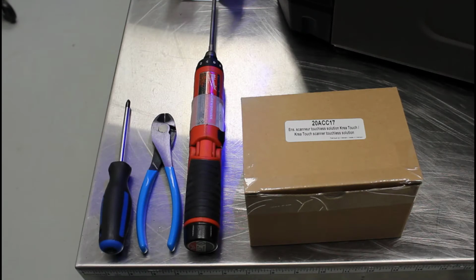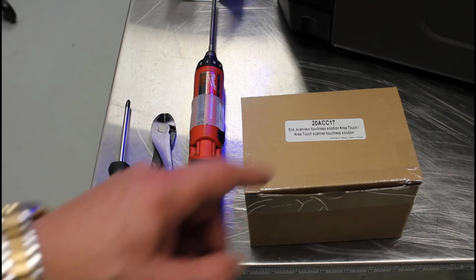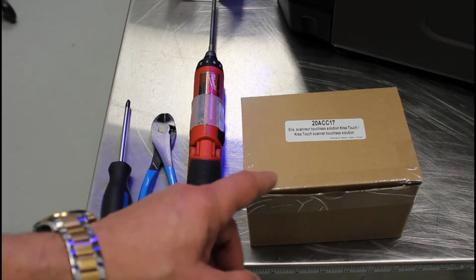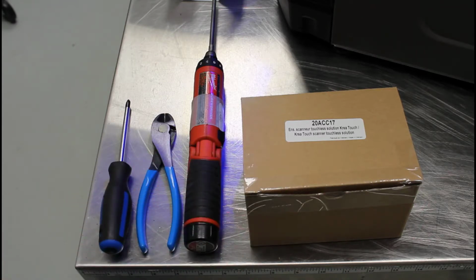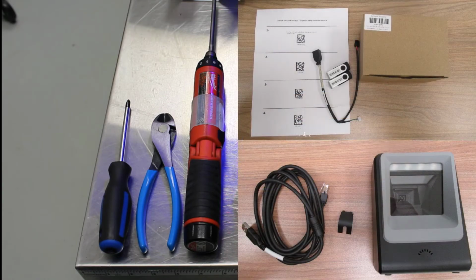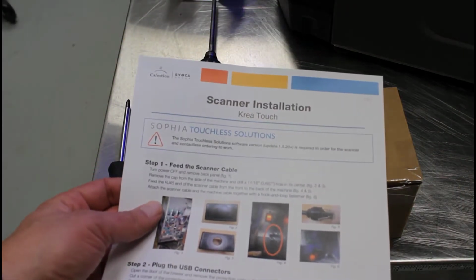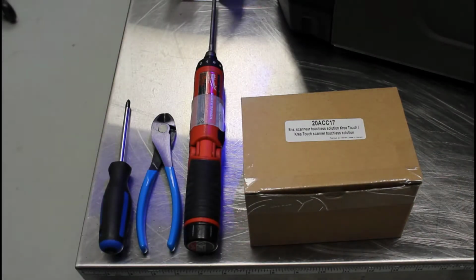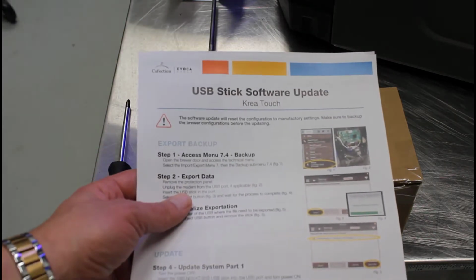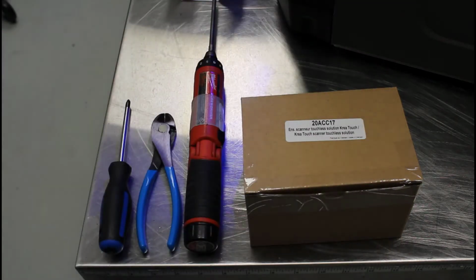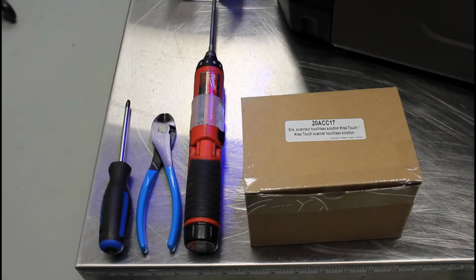You'll need a Phillips number 2 screwdriver, either electric or standard, up to you, a pair of cutters, and a kit. Inside the kit, 20ACC17, is the Krea Touch Scanner touchless solution. You'll have the scanner procedure inside that comes with it. But also you'll need the software update procedure in order to do the whole install of the scanner.